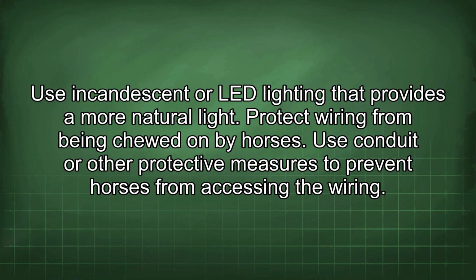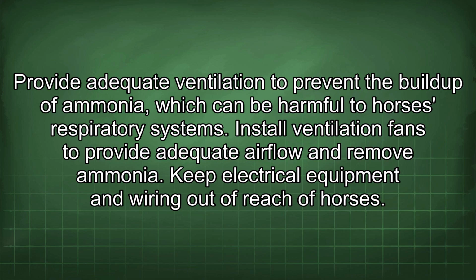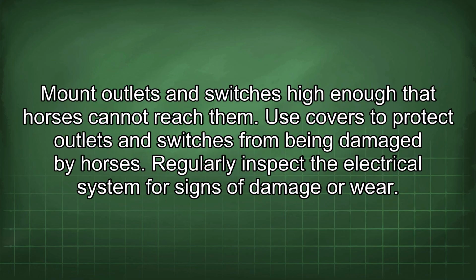Protect wiring from being chewed on by horses. Use conduit or other protective measures to prevent horses from accessing the wiring. Provide adequate ventilation to prevent the buildup of ammonia, which can be harmful to horses' respiratory systems. Install ventilation fans to provide adequate airflow and remove ammonia. Keep electrical equipment and wiring out of reach of horses. Mount outlets and switches high enough that horses cannot reach them. Use covers to protect outlets and switches from being damaged by horses.